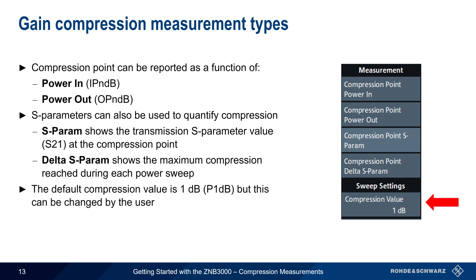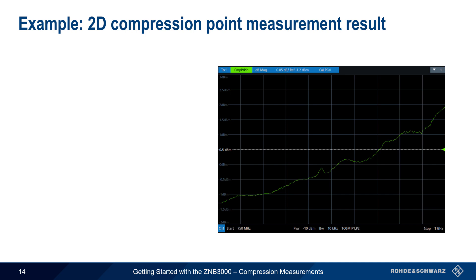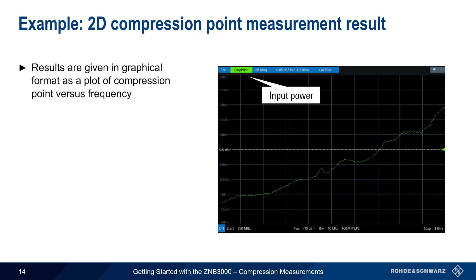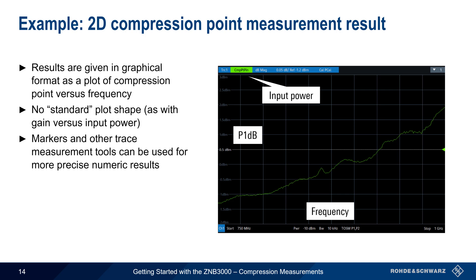The default compression point for all of these types is 1 dB, but this can be changed by the user. Here is an example of a 2D gain compression measurement for Input Power Compression Point. The results are given graphically as a plot of compression point — here P1dB — as a function of frequency. Unlike traditional gain compression curves of gain versus input power, this 2D compression measurement curve doesn't have a standard shape, although compression point often changes as a function of frequency. Markers and other standard trace measurement or statistical tools can be used to obtain more precise numeric results if needed.